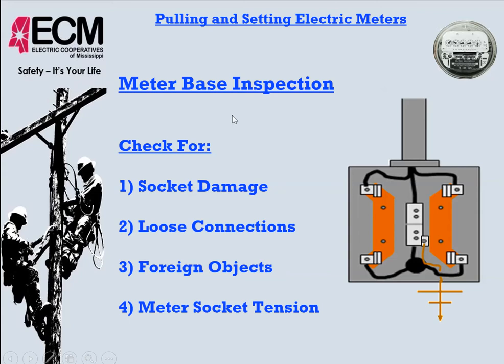Meter base inspection, check for socket damage. Now there are a lot of things that can happen to this meter socket. One of the things that can happen in the way of damage is that these plastic insulators can become cracked or broken. Over a period of time they become deteriorated by the weather, the ozone, sunlight, if they remain vacant for quite a while. Another way that they can cause us problems is if they become broken.